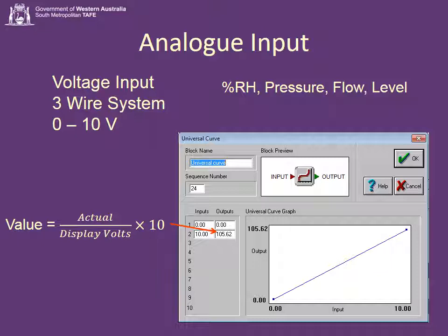And that's great, except for there are voltage drops. So it's never perfectly accurate. We need to make a very slight change. So what we do is we measure the value and we look to see what voltage there is. We divide the value by the voltage, multiply by 10, and that's what we shove into that box. I better run through an example.